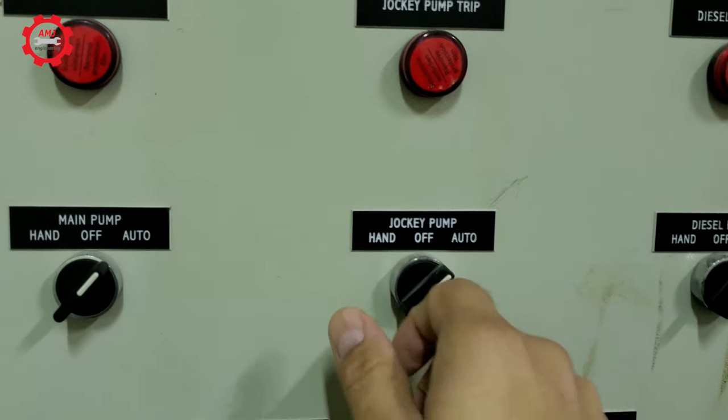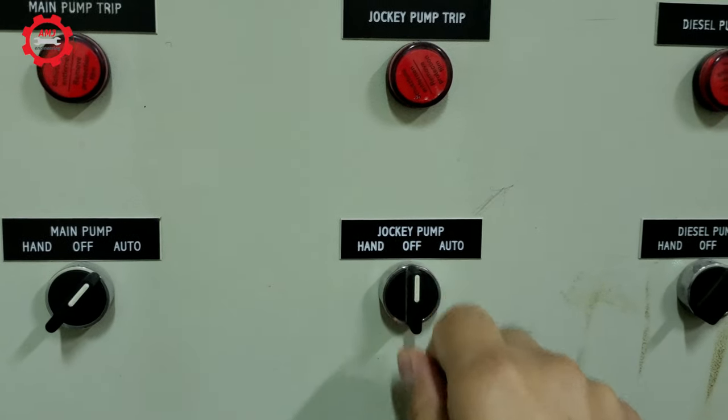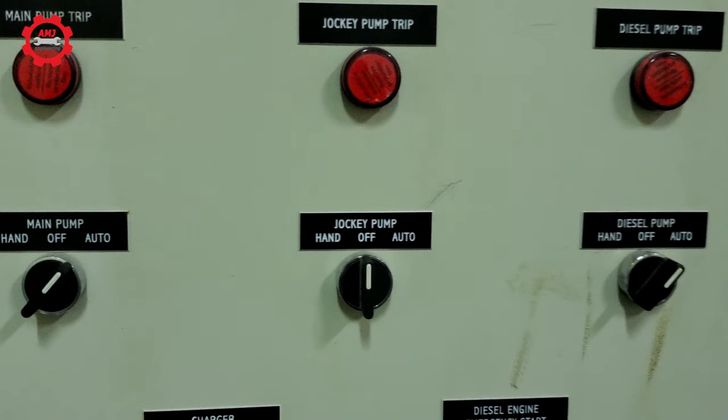Now, in order to test the main pump, I am going to turn the jockey pump controller to the off position, so that the jockey pump will not start when the system pressure decreases to 78 psi. That will allow the system pressure to decrease more and the main pump should start at 73 psi or 5 bars, as we said the start pressure for main pump is 5 psi less than jockey pump start pressure.